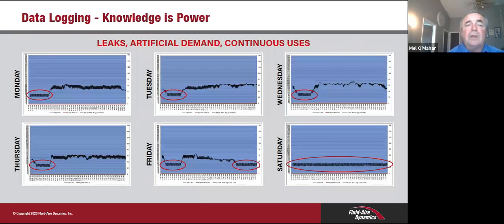So a lot of things come up on these data log reports. If you look at Monday on the chart, you'll see that circled area, that's showing leakage. That's the compressor probably started up 2 or 3 hours before the plant is up and running, and that's showing leakage. And you'll see the same thing on Tuesday and every day of the week there. What's interesting is you go over to Saturday and you see that it's all leakage. They probably kept the data logger on, which we typically do, because it's a quick way to find out how high a leakage rate a customer has right off the bat. Without even getting an ultrasonic gun on it, you can see what kind of percentage you have.